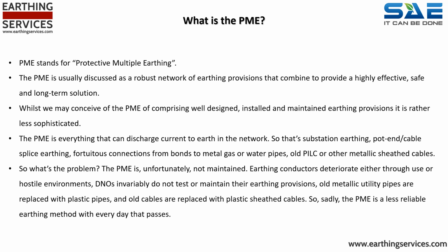PME stands for Protective Multiple Earthing. PME is usually discussed as a robust network of earthing provisions that combine to provide a highly effective, safe, and long-term solution. Whilst we may conceive of the PME as comprising well-designed, installed, and maintained earthing provisions, it is rather less sophisticated. The PME is everything that can discharge current to earth in the network.